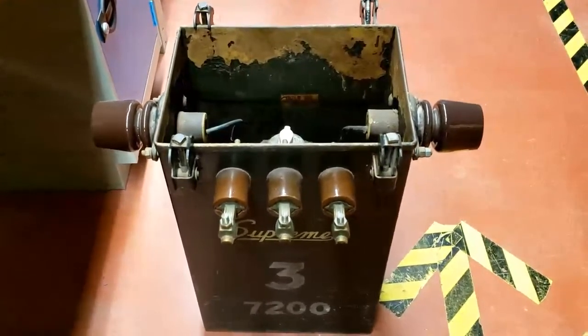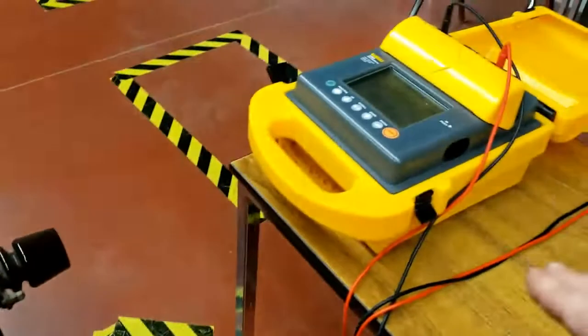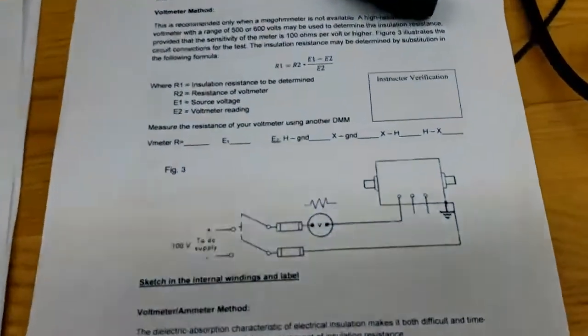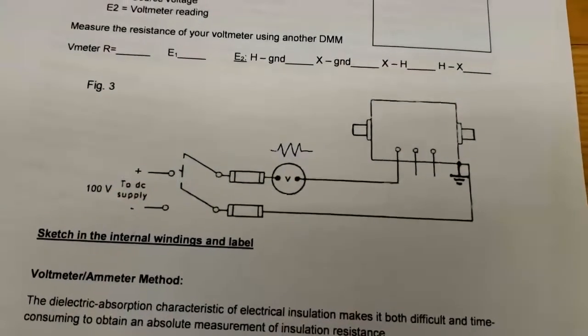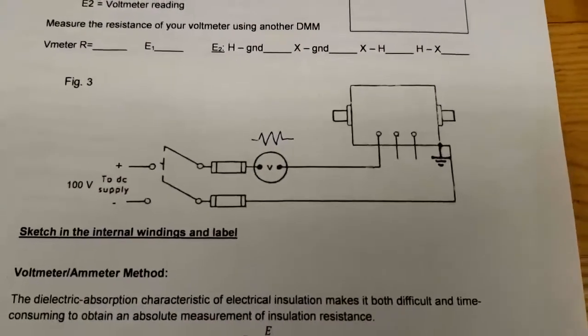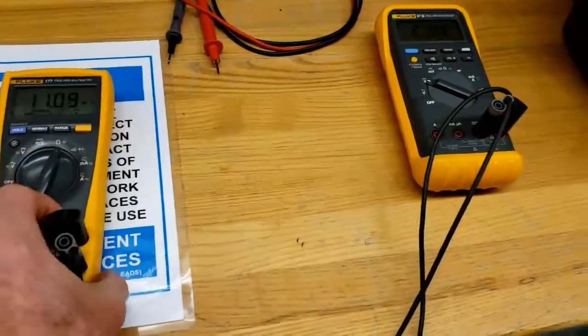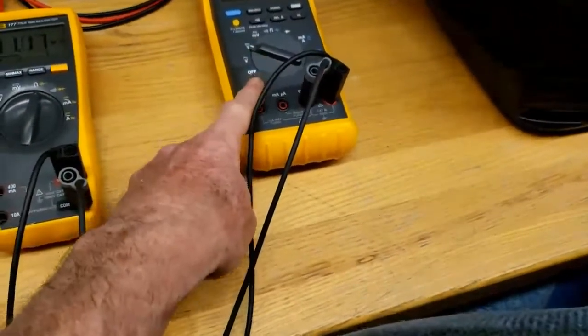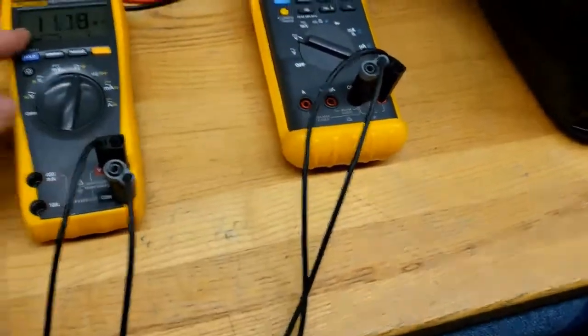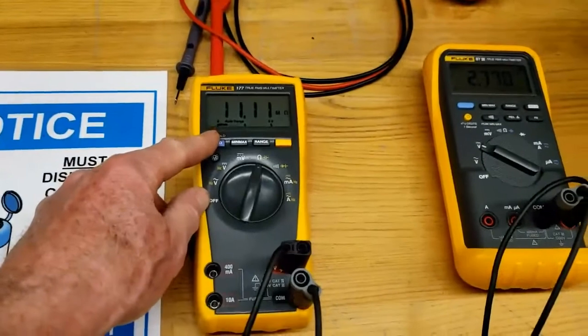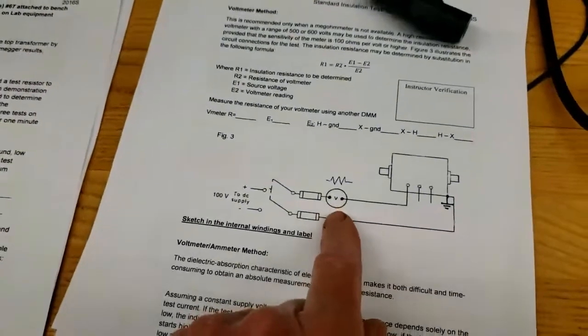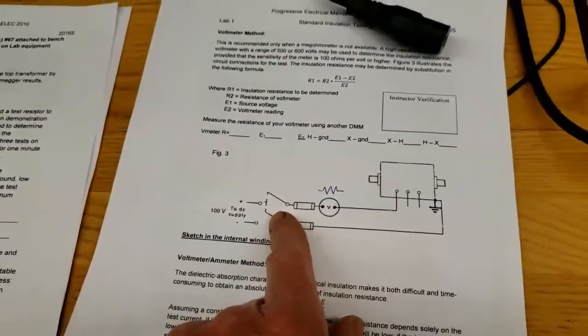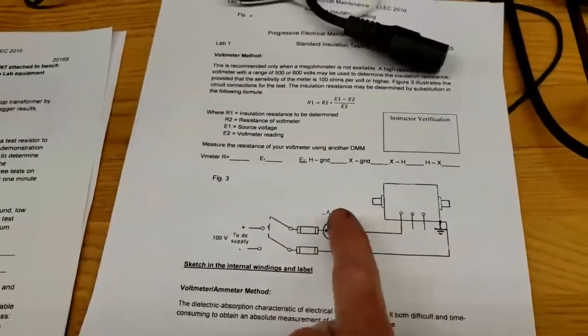So that's the purpose of preventative maintenance, is checking and testing and recording and noticing trends that predict some type of failure. So you're going to use three methods. You're going to use the Megger method. Then you're going to use a voltmeter method. All you're going to do is put a voltmeter in series, so it acts like a resistor. But before you put it in series, you're going to take another voltmeter and hook it up and set your voltmeter to read DC volts and see what the resistance is. This one is about 11.11 meg ohms. So effectively, you're putting an 11 meg ohm resistor in here, and you're going to provide 100 volts DC, and you're going low side to ground. Well, you're going to do a couple of readings.